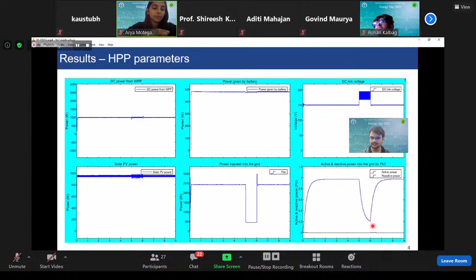At 5 seconds, a voltage dip of 0.8 per unit, that is a system voltage of 0.2 per unit, is given to the system. We can see the power injection is reduced, but the power coming from the sources is the same. That is why we see an increment in the DC link voltage during that operation. So we use crowbar protection. Whenever the DC link voltage increases beyond its limit, the extra power coming into the DC link is dissipated through the resistance of the crowbar protection. Here we can see the active and reactive power injection depending upon the grid requirements, and a small increment in the reactive power at the time of voltage decrement.